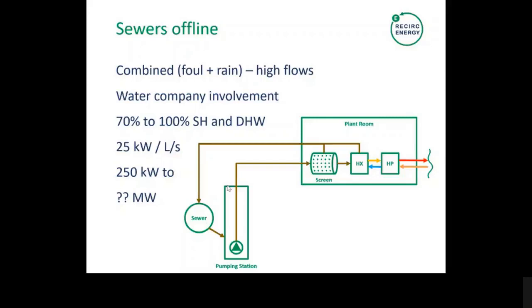Obviously the heat exchanger in question is a specialized bit of kit that is either self-cleaning or can be incorporated with cleaning-in-place technology to keep the surfaces of the plate heat exchanger or shell and tube, etc. clean, so the efficiency is kept high. The advantage with sewers is there's a lot more flow, so we're talking about delivering anywhere from 70% to 100% of the space heating and domestic hot water demand of the end user, whatever that might be, a single building or a district heat network. In terms of kilowatts, due to the cooler temperature of the water, we're talking somewhere nearer 25 kilowatts per litre per second of wastewater.